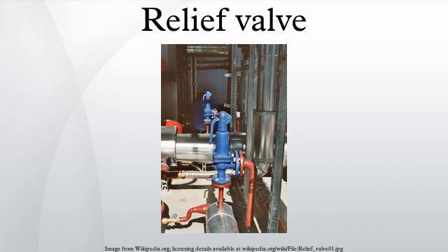As the fluid is diverted, the pressure inside the vessel will drop. Once it reaches the valve's reseating pressure, the valve will close. The blowdown is usually stated as a percentage of set pressure and refers to how much the pressure needs to drop before the valve reseats. The blowdown can vary from roughly 2 to 20%, and some valves have adjustable blowdowns.